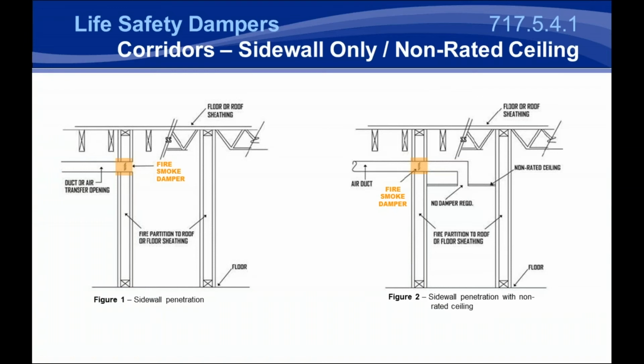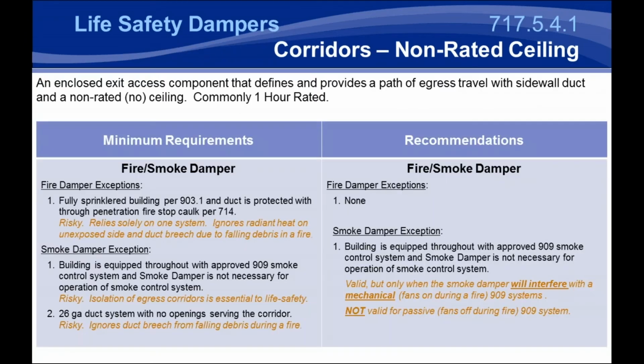Next, we'll get into corridors, and there's 3 types of corridors. I talked about tunnel-type corridors earlier. I won't spend a lot of time on those, but basically the 2 main types of corridors we're going to want to look at are corridors that are sidewall only, so there's no rated ceiling, or there's no penetration to the rated ceiling, or basically there's a drop ceiling, but it's not a rated ceiling. Typically, these are going to require a fire smoke damper. These are going to be the minimum and what we feel are the recommended requirements.